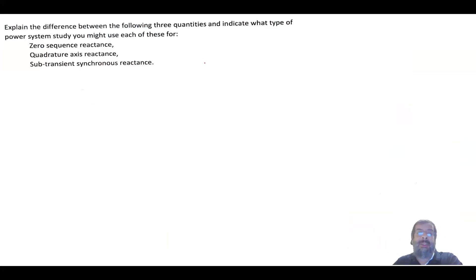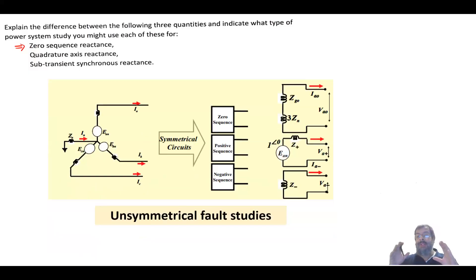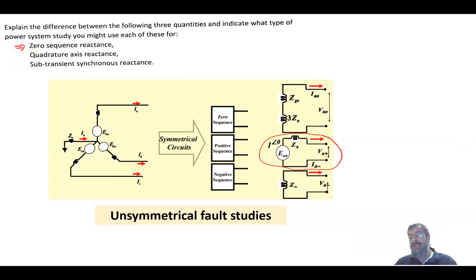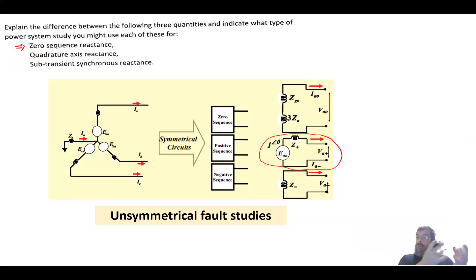We'll start with the zero sequence reactance. Under steady-state studies, we use a model with a voltage supply in series with the synchronous reactance — sometimes with a resistance, but most of the time we ignore it for power system studies. This is for steady-state analysis, which could be for load flow or symmetrical faults where the system is balanced. In that case we use only what we call the positive sequence.